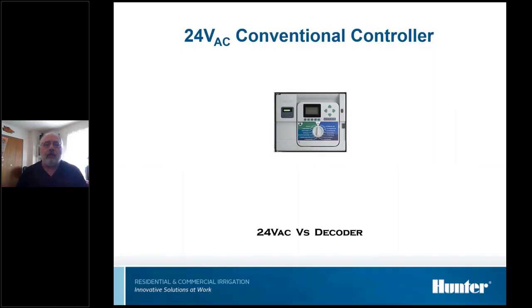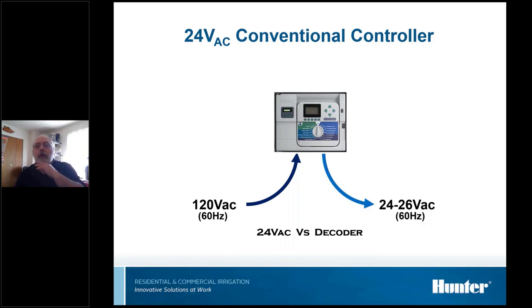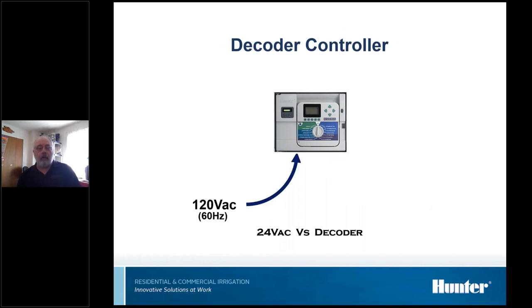Okay, so basically on a conventional system, we have 120 volts at 60 hertz coming into the controller, and then we come out with what we call 24 volts. It's usually 26 to 27 volts AC at 60 hertz coming out of them. And that's what conventional test equipment likes to see and knows how to read.